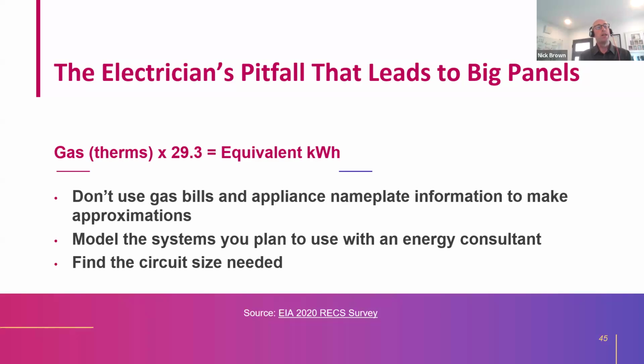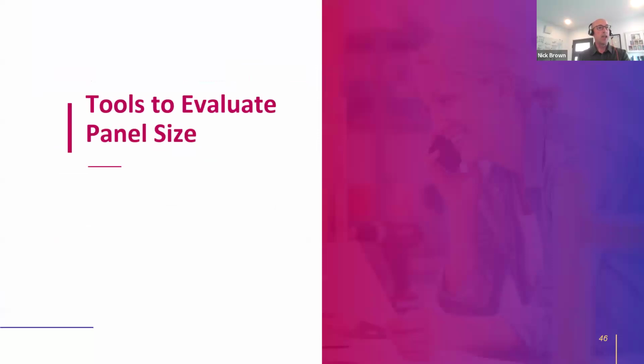Now, a pitfall that Robert and I have run into is this abstract conversion from gas to electric. Let's say you've got a mixed fuel house with a gas furnace and a gas water heater, and you're planning to electrify. If you just take gas usage times this abstract conversion factor and say this is how much electricity we're going to need, it's going to lead to way oversizing the panel. So what you want to do instead is find the electric systems that replace the gas systems, size them right, and then use that volts and amps to size your panel. Don't use that abstract sizing pitfall.